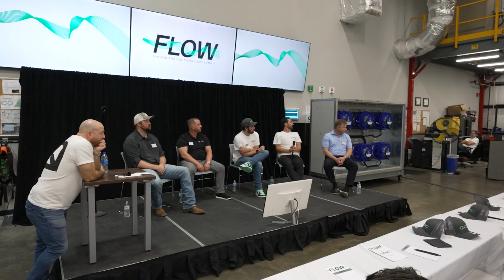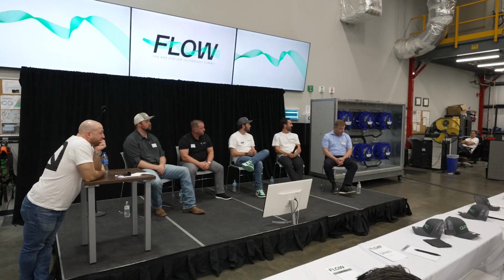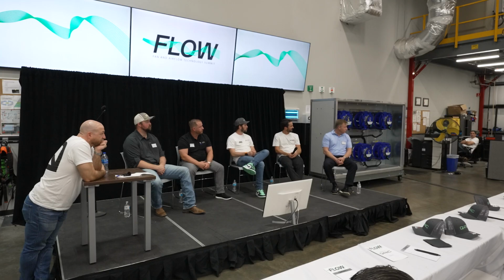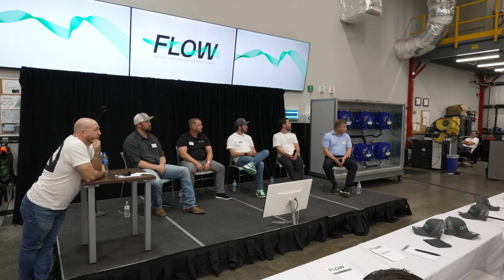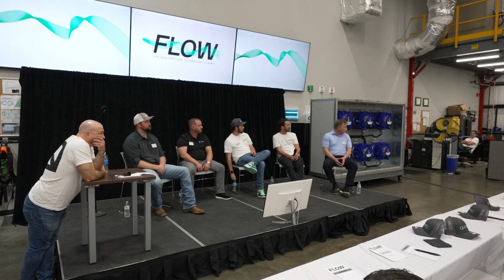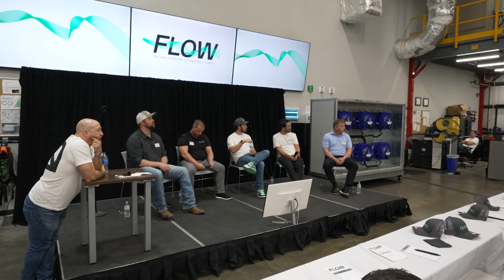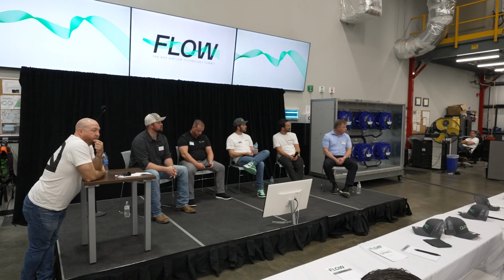We're up to 91 buildings, a mix of MOBs and medical facilities, all with traditional belt-driven motors, Baldor kind of stuff with drives. Of those, we've surveyed chill water valves, boiler systems, and motor and VFD combinations. I think over 64% are running at a moderate or significant impact to energy because they're not running efficiently, or the drive isn't referenced correctly.